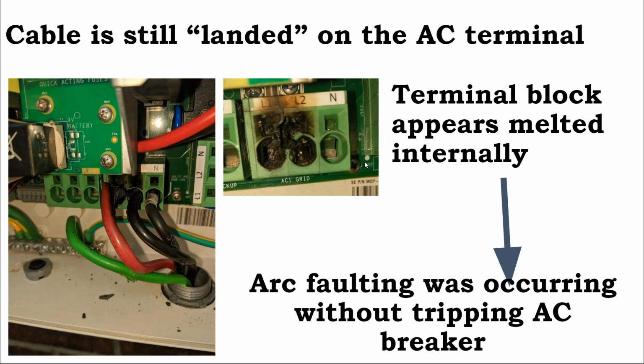All right, so the picture is worthwhile. You know what, we can see the heat from the cable. Amperage is a heat issue. Voltage is more of an explosive issue. And what we're seeing here is signs of melting rather than pulverization. This is an amperage issue.